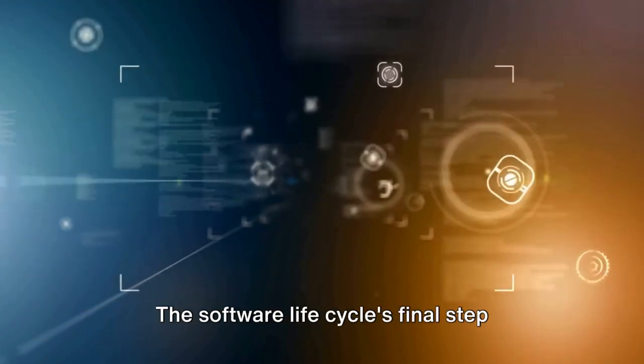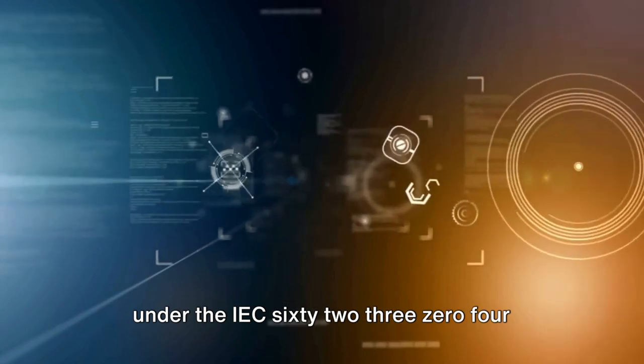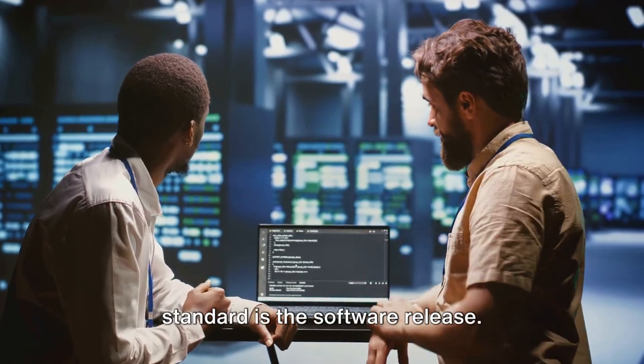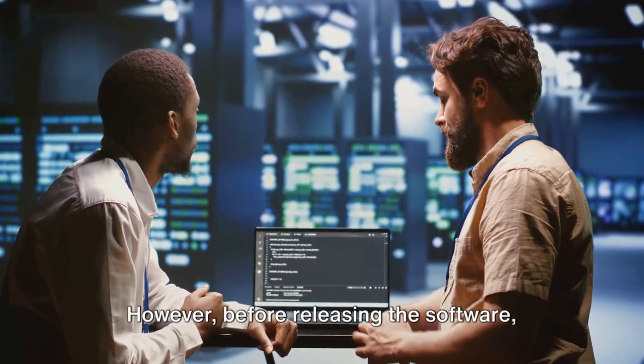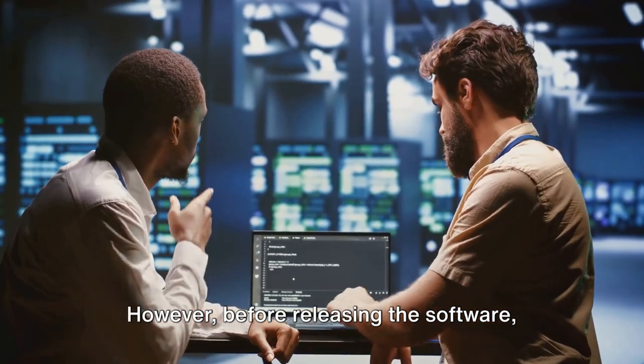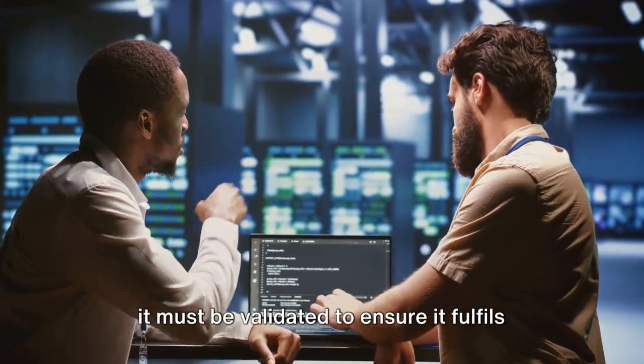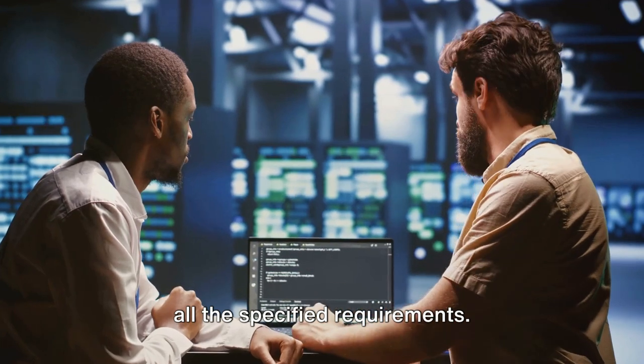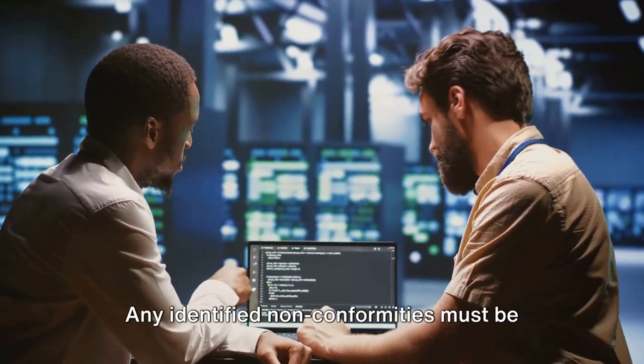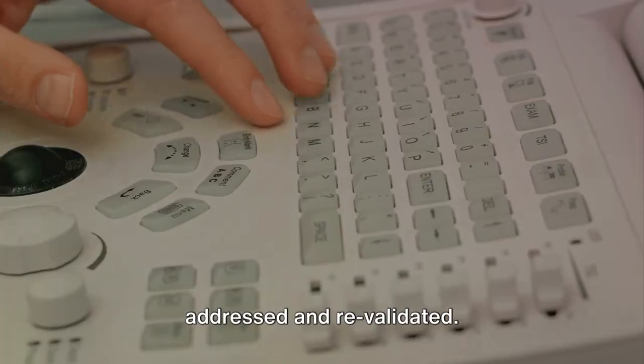The software lifecycle's final step under the IEC 62304 standard is the software release. However, before releasing the software, it must be validated to ensure it fulfills all the specified requirements. Any identified non-conformities must be addressed and revalidated.